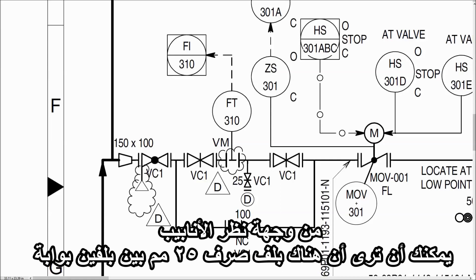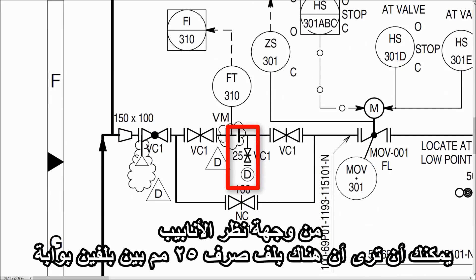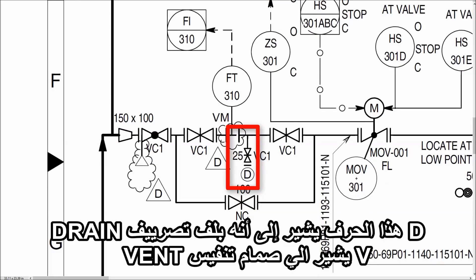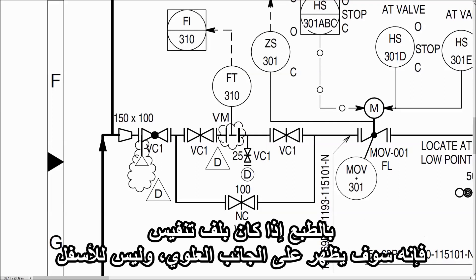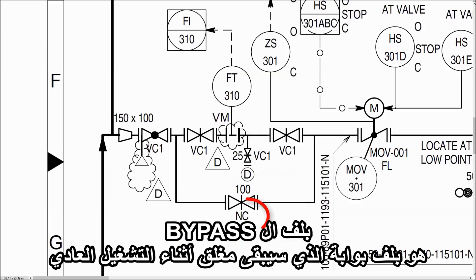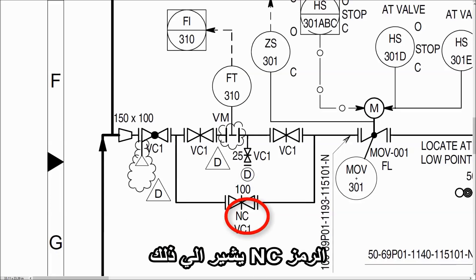From the piping point of view, you can see that there is a 25mm drain valve given in between the two gate valves. The letter D indicates that it is a drain valve, and if it is V then it is a vent valve. Of course, if it is a vent, it is shown on the top side, not on the bottom. The bypass valve is also a gate valve which will remain closed during normal operation. You can see the letter NC which indicates the same.